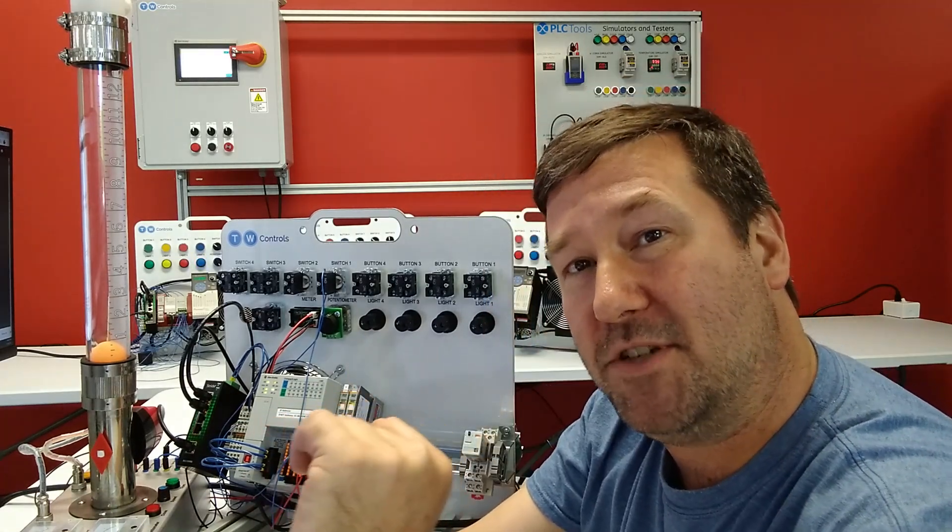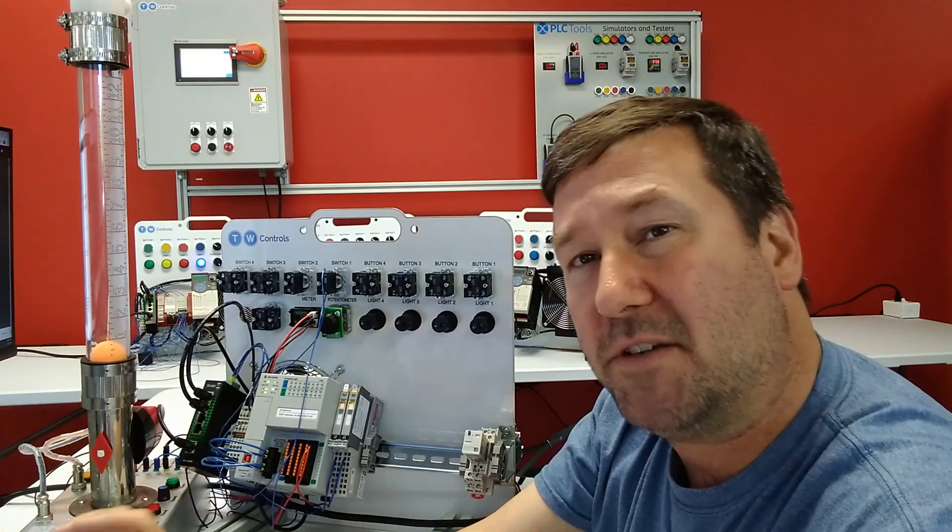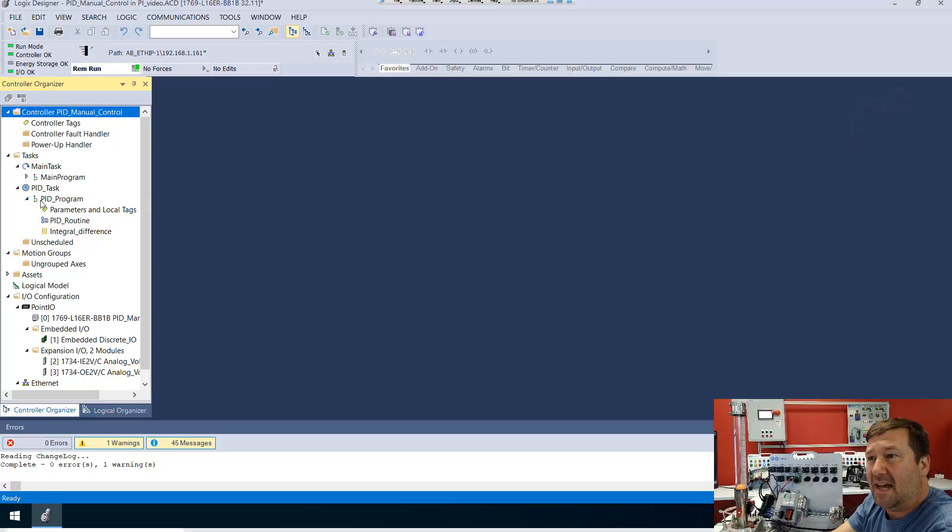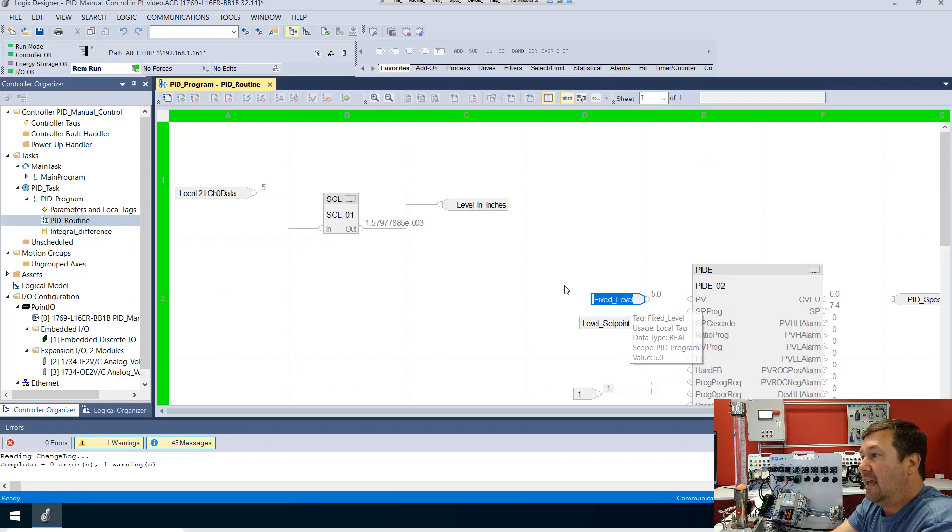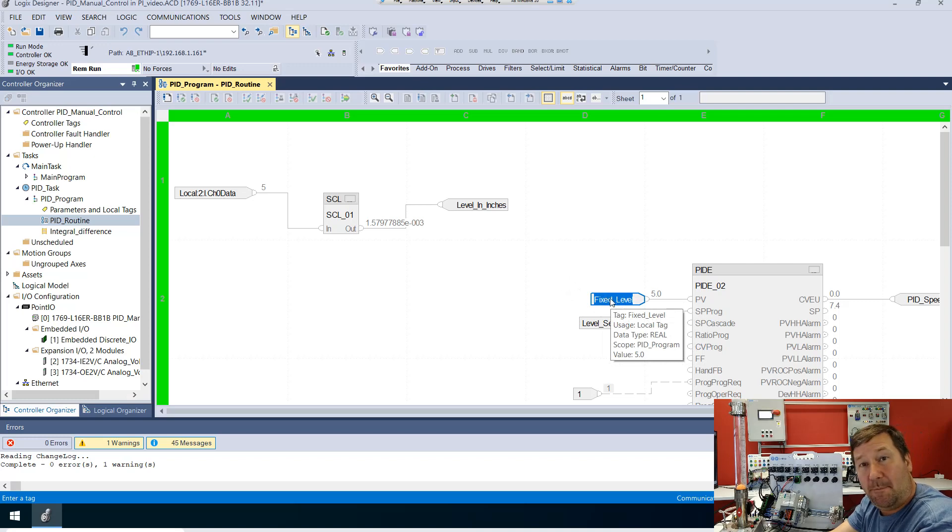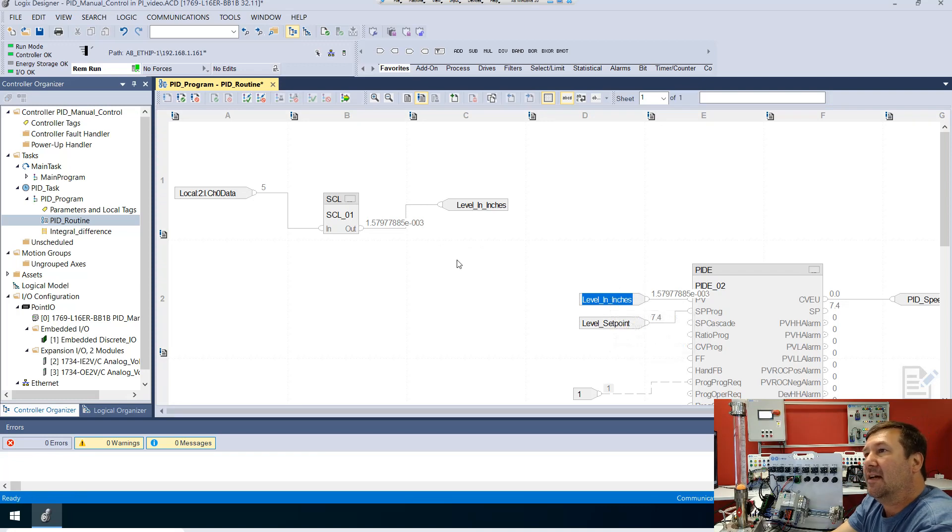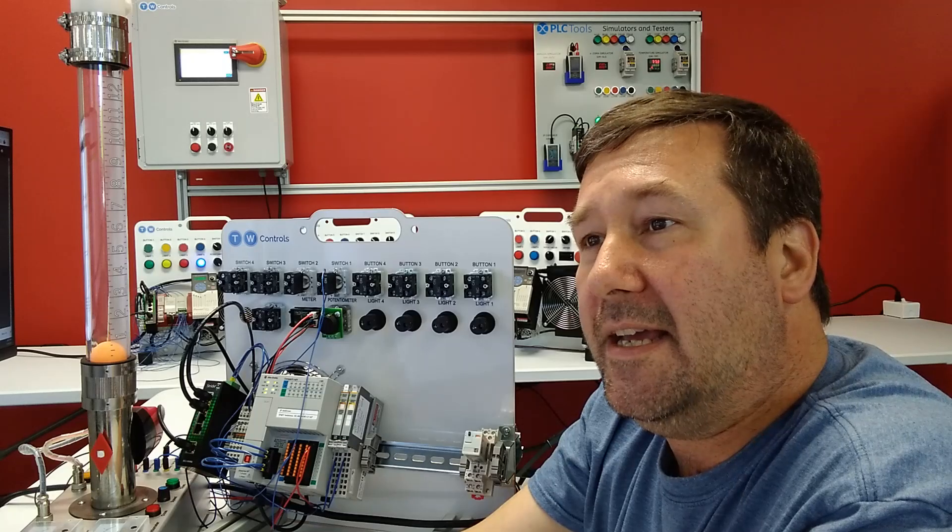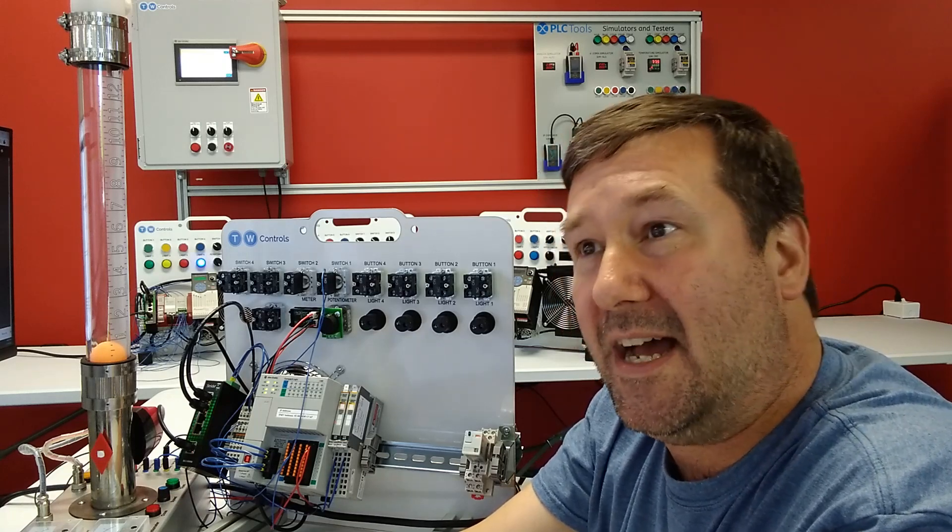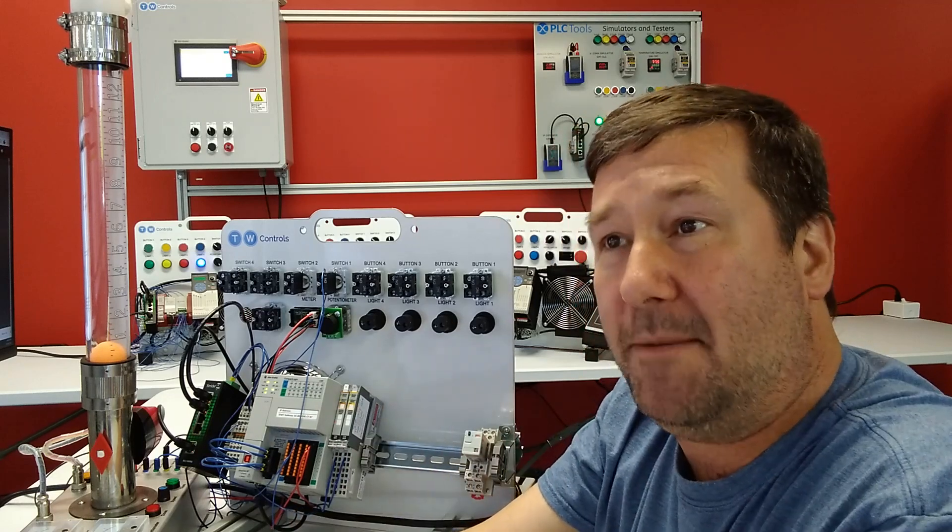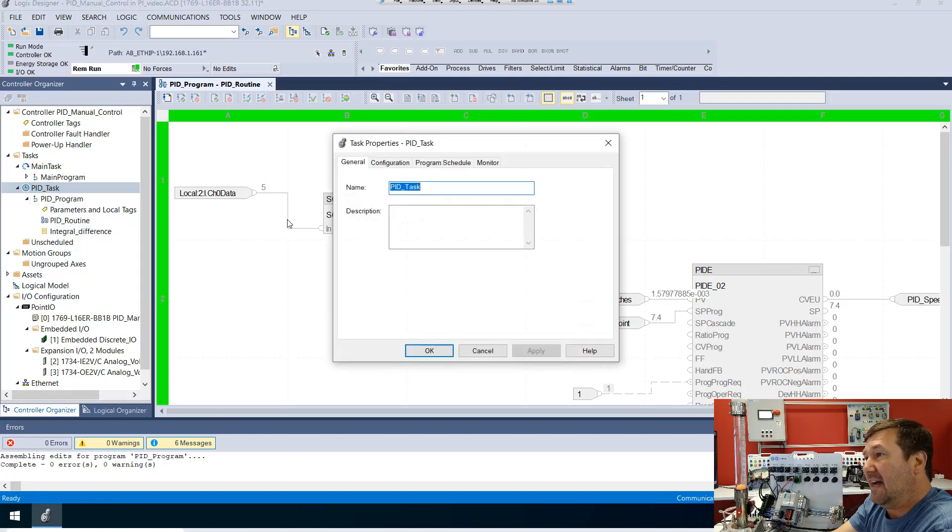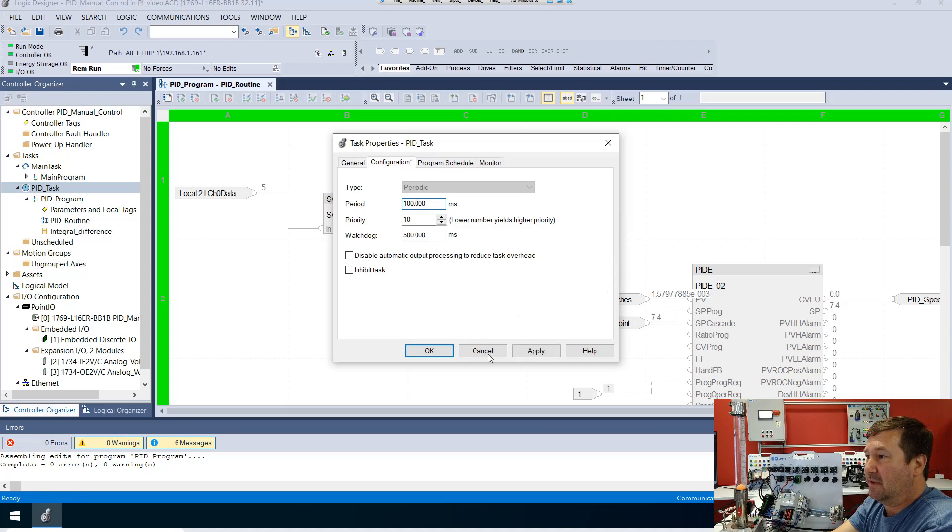So let's go through this. We need to make a few changes to our integral program from the last video because we made some programming changes to look specifically at what the integral does. Let's open up our PID program and go into the PID routine. On our PIDE instruction we have this fixed level we were using in our integral video. We need to put that back as our actual level in inches. Then we had changed our periodic task time to one second so we could slowly see what was happening, but I want to put that back to 100 milliseconds.